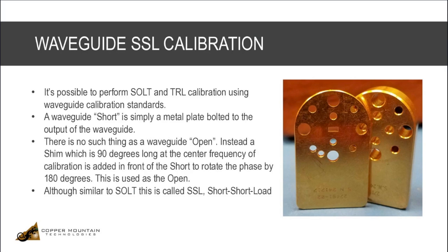Waveguide. All right, looks like we're getting a little short on time, but hopefully we can get through this. Waveguide, we do a couple different kinds of calibration. We can do a short open load like calibration. It's really called SSL, short short load.